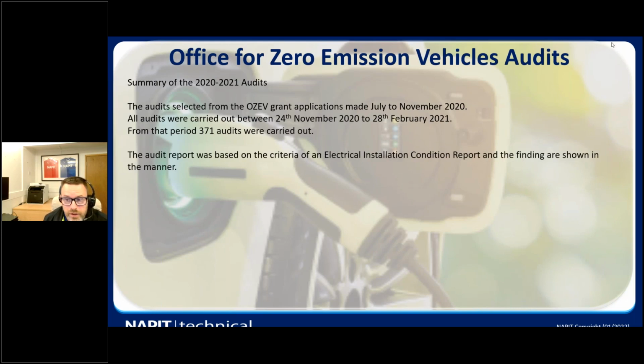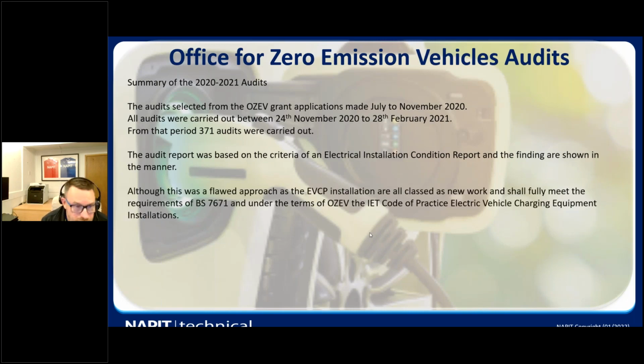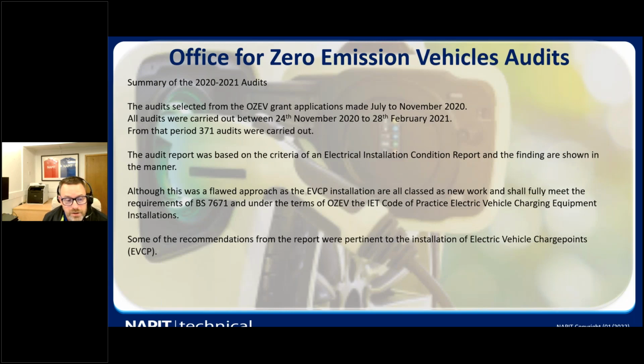The audits were based on electrical installation condition reports, and part of the findings of the audit report are based on the EICR style of reporting. We've all thought this was a flawed approach to the OZEV report on the EV charge points. It was to see if they meet the full requirements of 7671 and, under the terms of OZEV, the IET Code of Practice. But as we all know, EV charge points are brand new installations, and they must meet fully the requirements of 7671. Some recommendations in the report are pertinent to the installation of EV charge points.